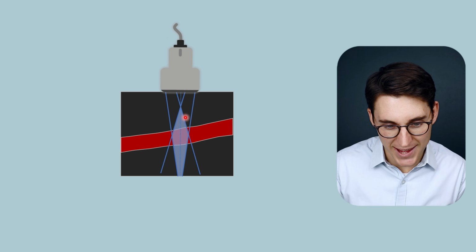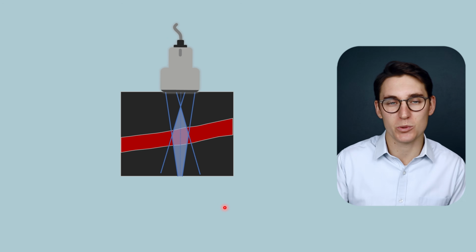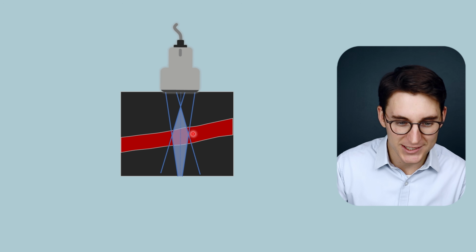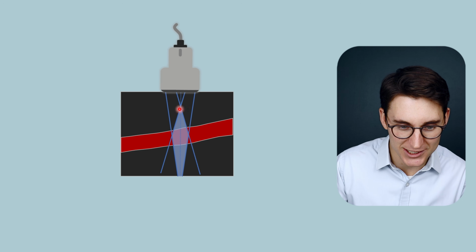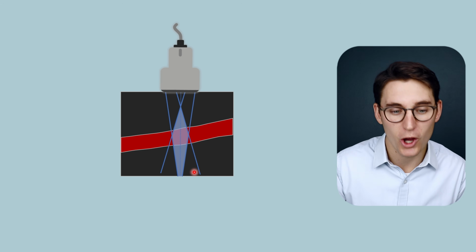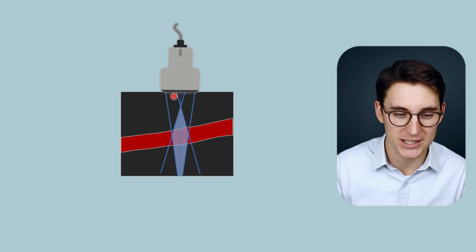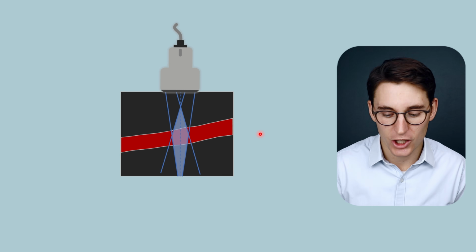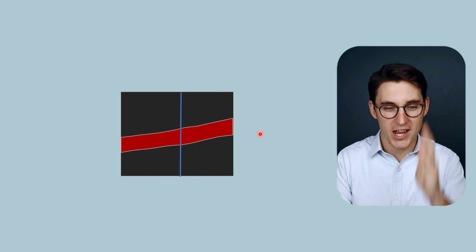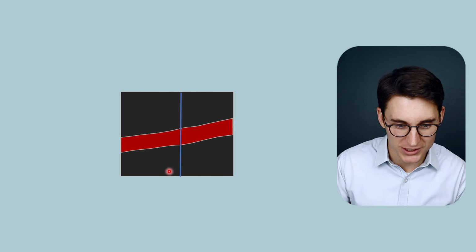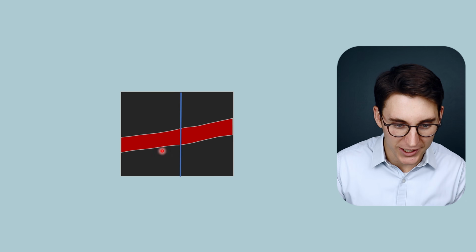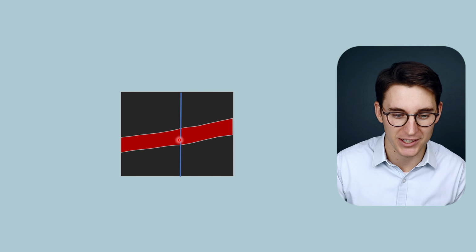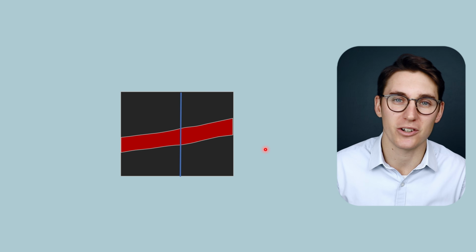Now you can see that the area sampled by the continuous wave ultrasound transducer elements is a large area here. Everything within here, anything that's moving within this diamond shape, will be returned back to our receiving transducer element. So when we look at our B-mode image and we draw a line down where we want to calculate the velocities, we are calculating all the velocities in this area here, not just the vessel that we are interested in.